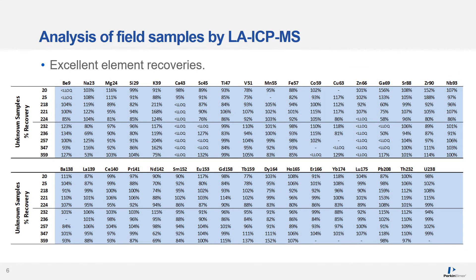This data shows the accuracy of NexION laser ablation ICP-MS when compared to acid digestions. In addition, it demonstrates the power of EDR, or extended dynamic range, of the NexION ICP-MS. Without the ability to dilute analytes, the extended dynamic range capability of the NexION ICP-MS allows us to acquire major element data while also acquiring trace elements in the same ablation.